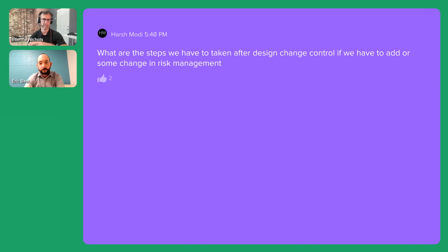Harsh asks, what are the steps we have to take after design control if we have some change in risk management? It kind of comes down to, well, what risk management change are you making? It's always easier to make things tighter than it is to loosen up your risk management requirements. So if you, for example, estimated that you were going to have a 1 in 100 rate of failure in your design process because you wanted to be conservative and estimate high, but as you get into your field data, you're seeing that your complaints are really more like 1 in 10,000, and you want to tighten that down in your risk management file, yeah, you can do that. You put it through change controls and make sure you've touched everything that risk file touches to ratchet that down. And then that's now your trip and your post-market process for that particular complaint, or that particular risk category, or wherever else it touches. Again, it's going to be largely determined by your change control process, and stuff like that is something you can do.